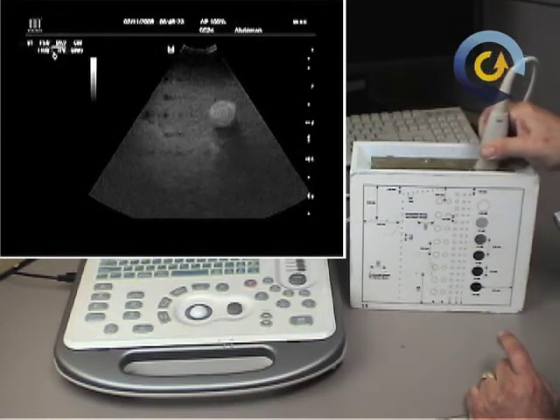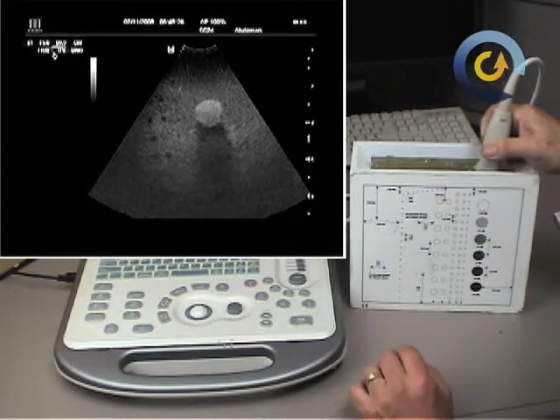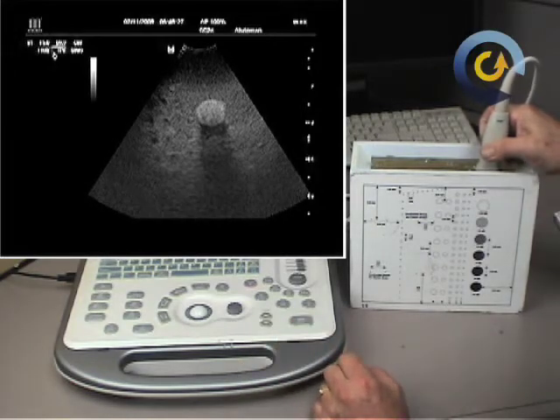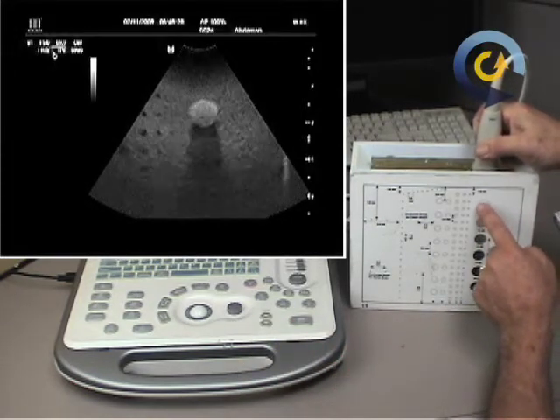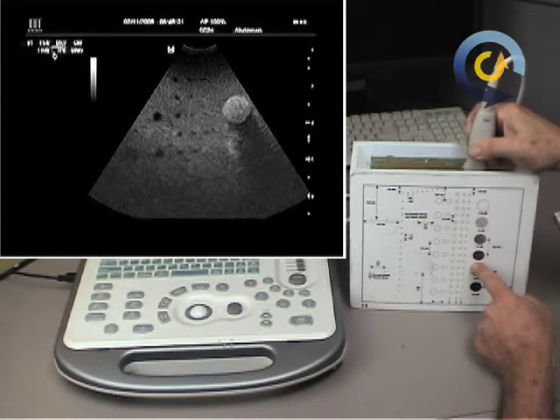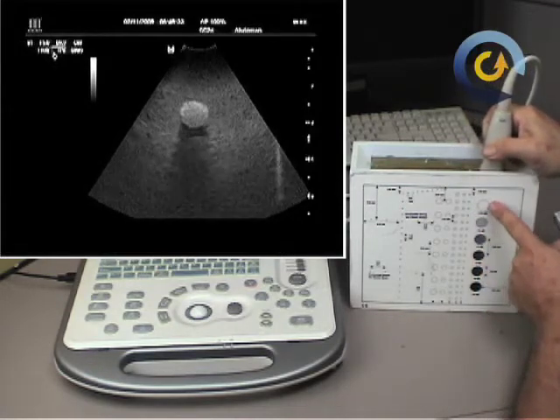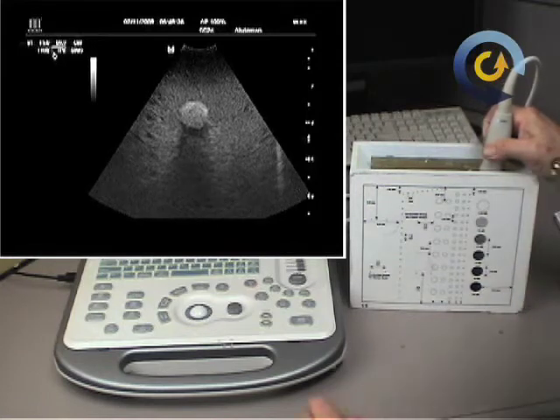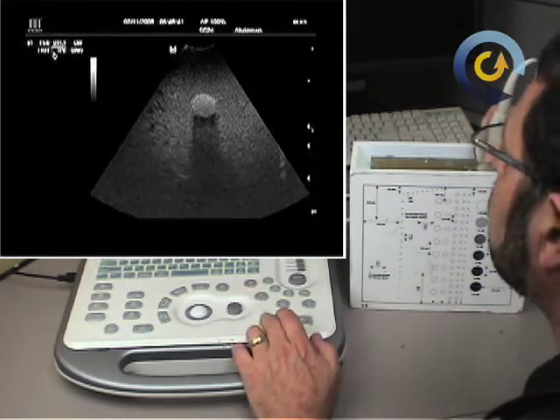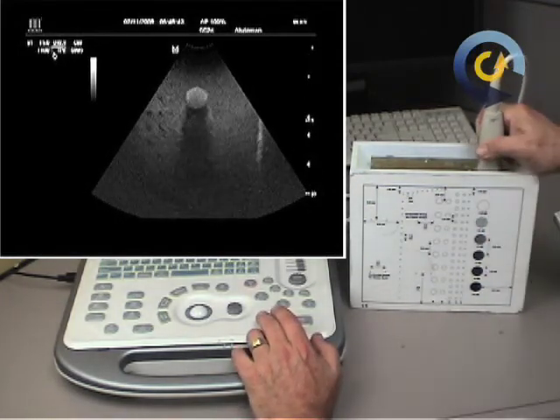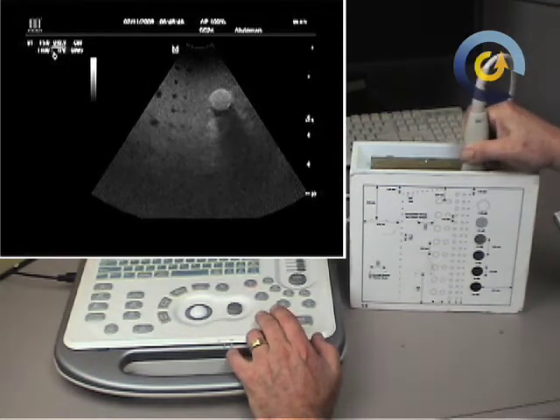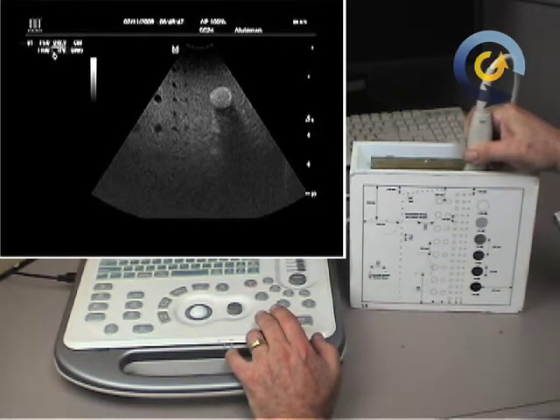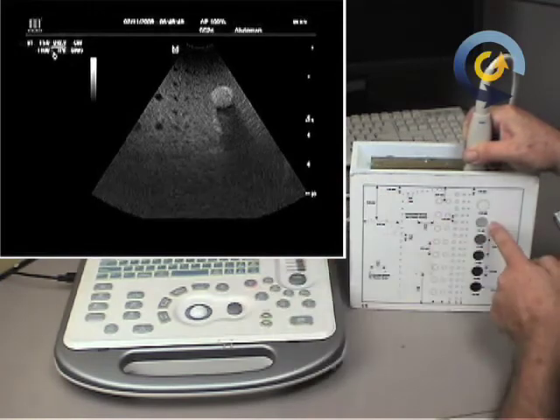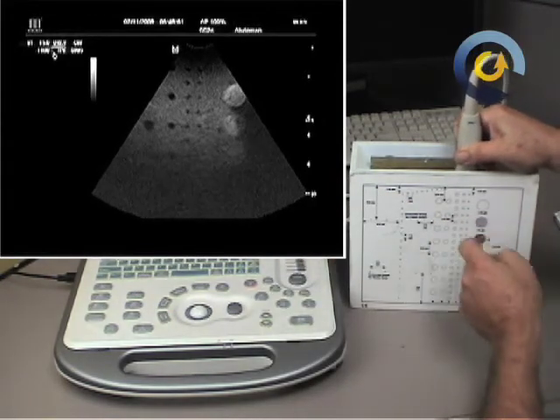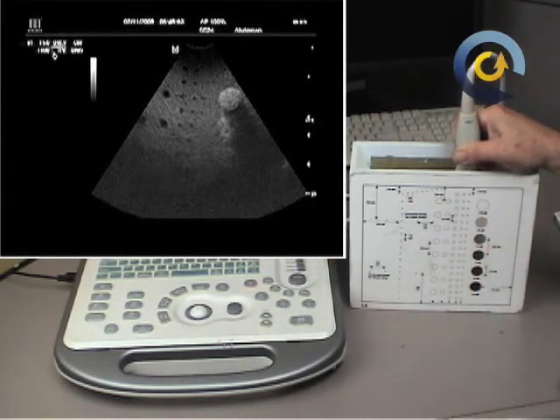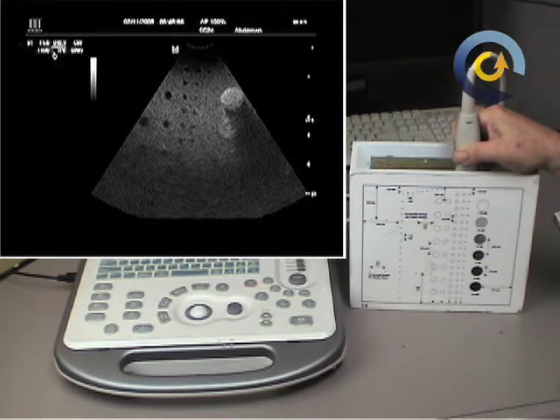Going back over to this side, this transducer is a higher frequency and we're not going to be able to get the depth that we probably want. What you'd like to be able to do is see a multitude of the rods running down the side and be able to see them go from lighter to darker all the way down. A higher frequency transducer will not go as deep in the body as a lower frequency transducer, and that's why we're not able to see these plexiglass rods down here very well. If I get off to the side, I can see them better, and with the linear transducer I would see them a little bit better as well.